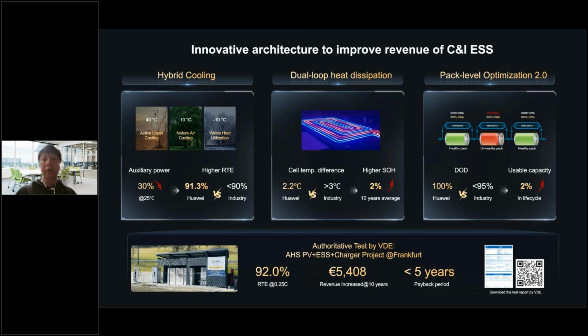And also for the cell temperature differences, as we mentioned, we have this dual loop heat dissipation. So the temperature difference between the battery cells inside of the battery pack is low. The cell temperature difference for Huawei ESS is only 2.2 degrees centigrade, but for others, the industry average is about 3 degrees centigrade. As we mentioned, the SOH for Huawei ESS is about 2% higher during the 10 years lifetime. And also because we have 100% DOD, thanks to the pack level optimization technologies, whereas the industry average normally reserves some of the capacity of their ESS, about 95% DOD. So the usable capacity for Huawei ESS during its lifetime is about 2% higher than the other ESS.